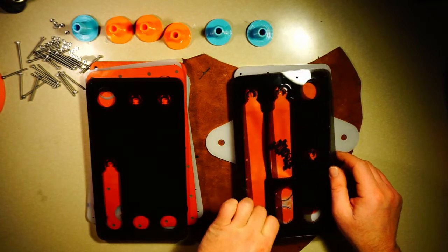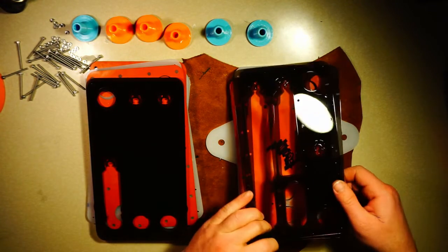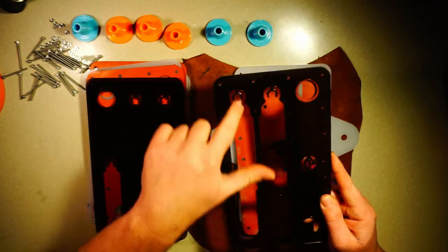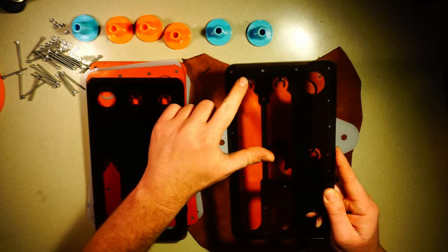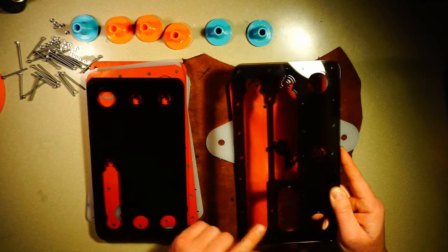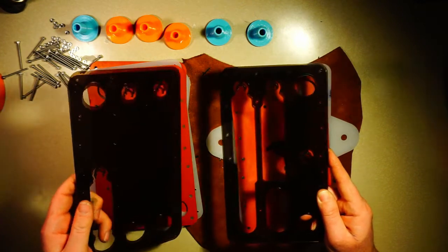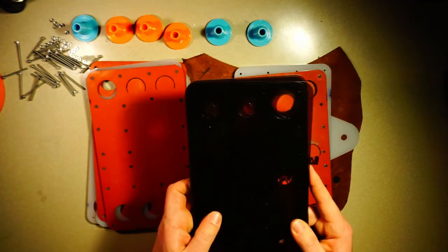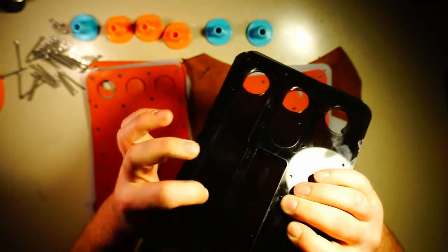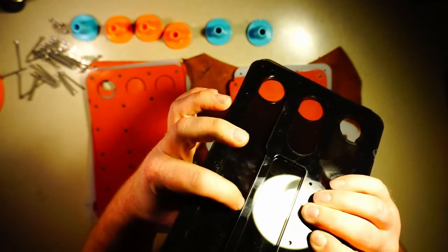Let's get to something more interesting. Here we have the PEEP chamber and the overpressure and patient chamber. Again, this leads out to the overpressure, this leads out to the PEEP, and this is coming in from the patient.